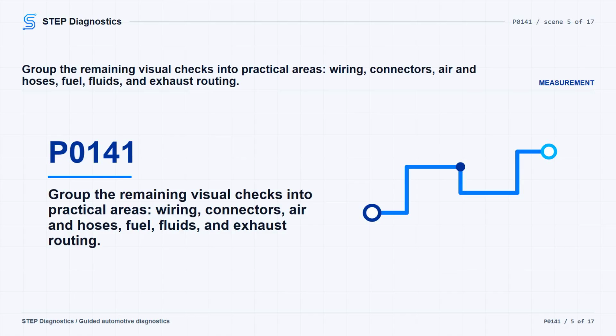Check fuel quality for octane, contamination, and winter or summer blend. Inspect the fuel tank, fuel lines, and fuel system for damage, leaks, and routing. Check coolant level and quality with the engine at the correct operating temperature. Check oil level and quality for contamination and maintenance condition. And inspect the exhaust system for damage, restriction, and routing problems.